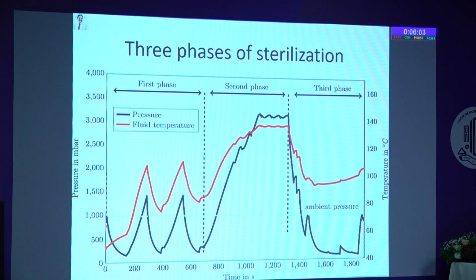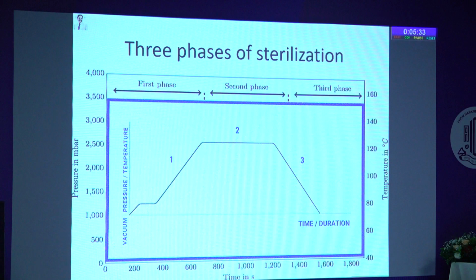There are three phases of sterilization. In the first phase, the pressure increases and the fluid temperature increases, so there is heating of the water. In the second phase, the pressure increases within that closed chamber, and when the pressure increases, there are a lot of changes happening. The steam is produced, and this steam gets into contact with the consumables, instruments, and whatever we place in the chamber. So essentially, we are dealing with three important parameters: the vacuum, pressure, and temperature, given over a period of time.